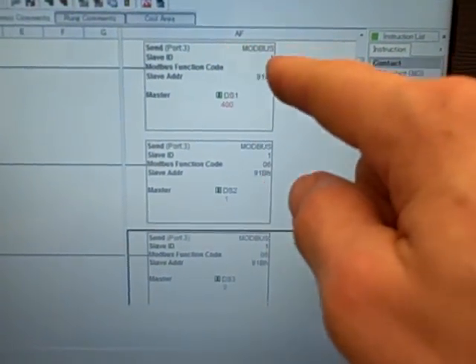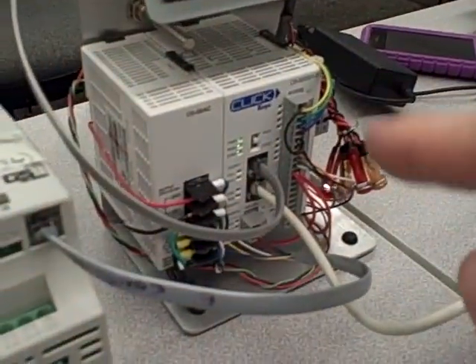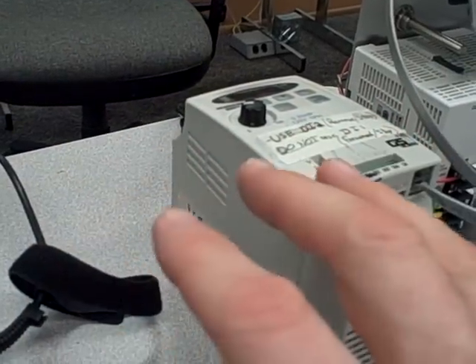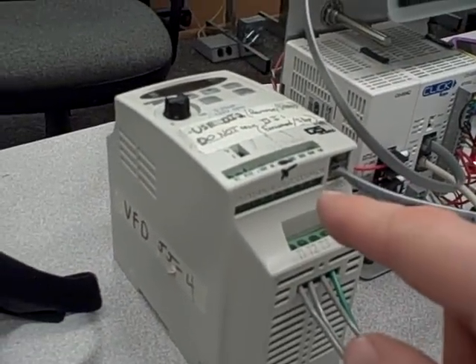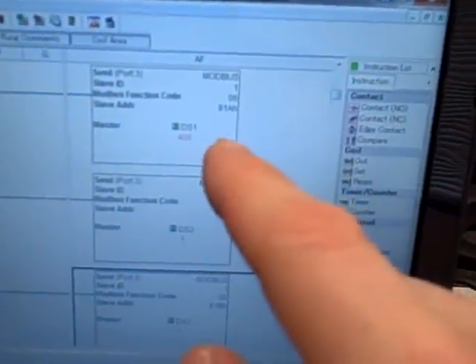Here's how we're accomplishing this. If we take a look at the PLC program, we see we have three Modbus send instructions. They're all sending out of port number 3 in the PLC, and they're sending to the same slave address, slave number 1, which is our VFD slave number. We could have multiple VFDs or multiple Modbus devices all daisy-chained on the same 2-wire network, each one with a different slave address. That's why it's important for this to be configured to the right slave address, and for the instructions to be talking to the right address.